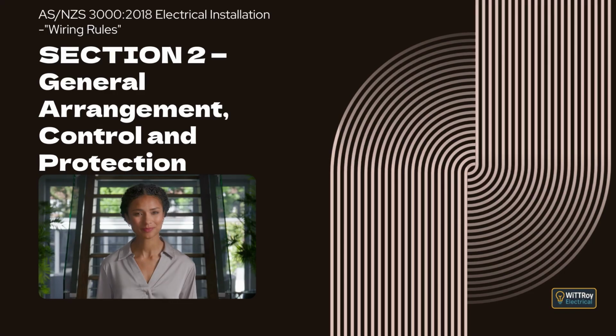Clause 2.9.2 Type. Any AFDD used in an installation must comply with standard IEC 62606. This ensures the device can correctly detect and disconnect arcing faults. Clause 2.9.3 Rating. The AFDD must have a load current rating that is at least equal to the circuit protective device it works with. In other words, it must be sized so it can safely operate on that circuit. Clause 2.9.4 Arrangement. The AFDD must be installed at the switchboard where the final subcircuit begins. This gives full protection for the entire circuit.